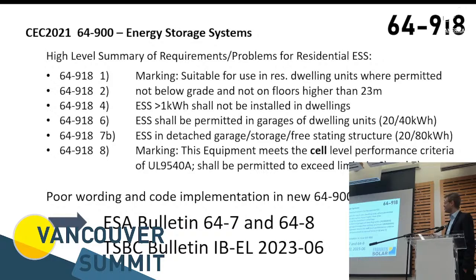Then it can be permitted to be installed in garages, as I mentioned, detached or attached to the dwelling. You have certain capacity limits at that point. If the structure or the garage is completely detached with a minimum distance of 1 meter, you can even do more capacity. So in that case, it's up to 80 kilowatt hours. And then the hardest one, that this equipment meets the cell level performance criteria of UL 9540A, which does not exist in the industry. And then you can actually exceed the capacity limits here. So we have a lot of restrictions, and it's pretty much impossible, as it's written right now, to do anything. Huge problem. And it's all about the poor wording when it was implemented in the 2021 code. There are some rewording efforts in the 2024 code, and we will see how that will affect future installations, and it gets a little bit easier.